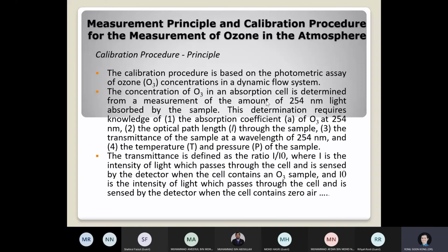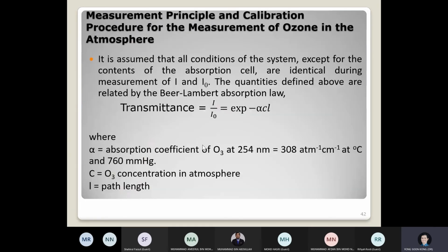Now, in this technique, it is slightly different than NDIR, in which it differs in this way. Earlier, when we discussed carbon monoxide, we detected its absorbance, but for ozone, we detect its transmittance. It is interrelated simply because when you have more absorbance, you have less transmittance.